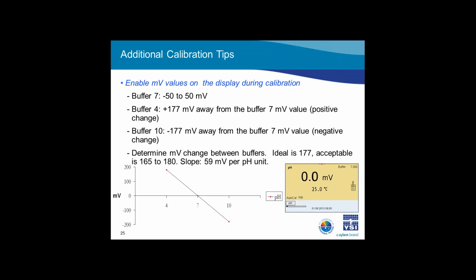In buffer 4, we are looking for a positive change in the millivolt value of 165 to 180, with 177 being the ideal. In buffer 10, we are looking for a negative change in the millivolt value of 165 to 180. For example, if we get a millivolt value of -10 in buffer 7, we would expect a millivolt value of 167 in buffer 4 and -187 in buffer 10.